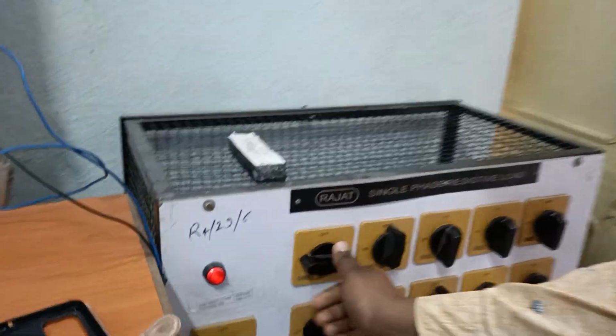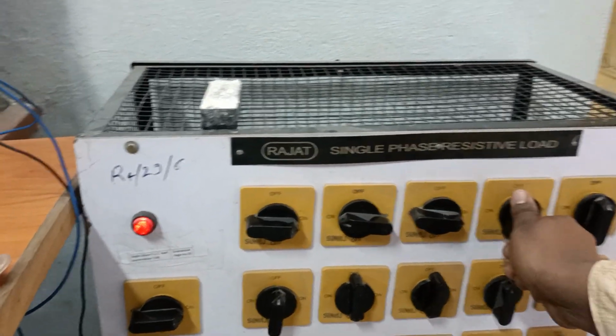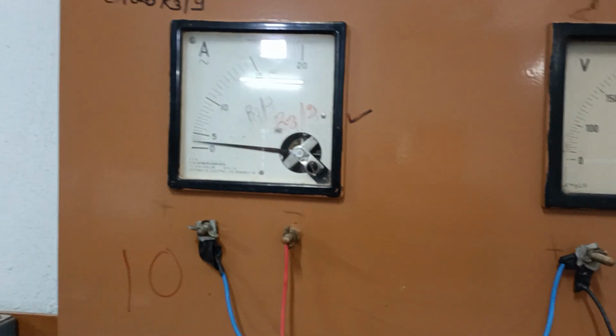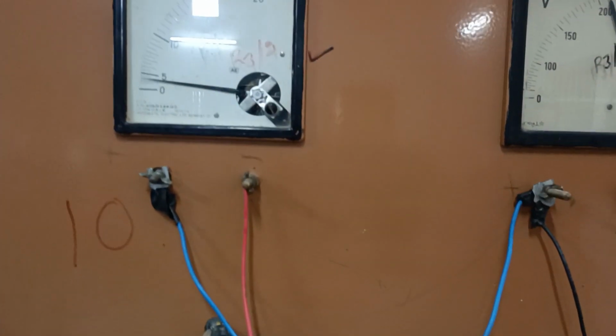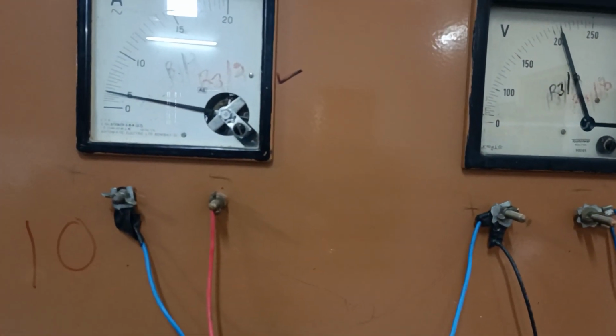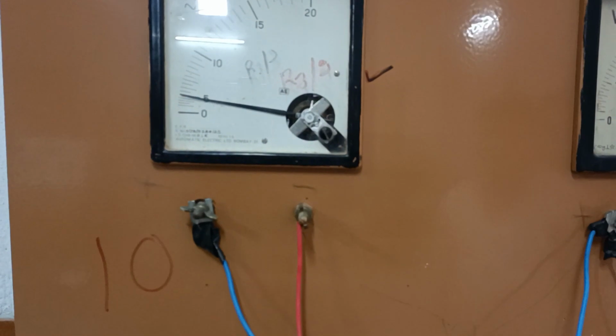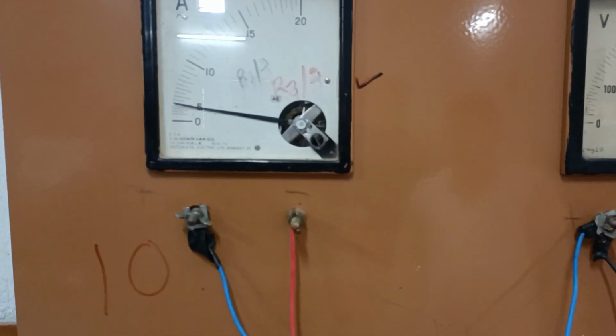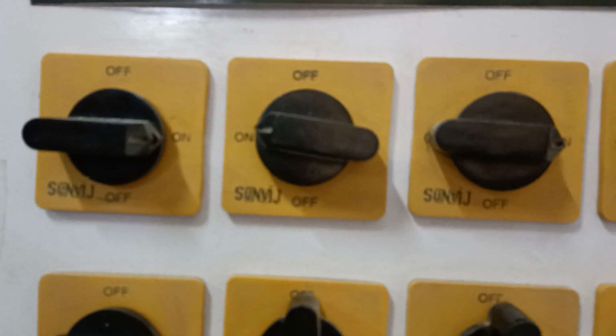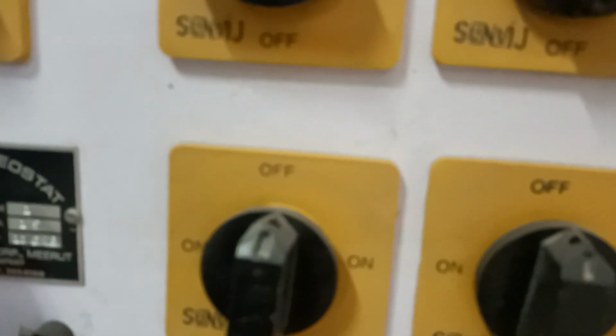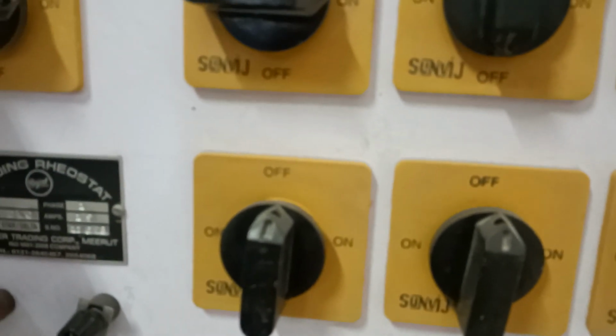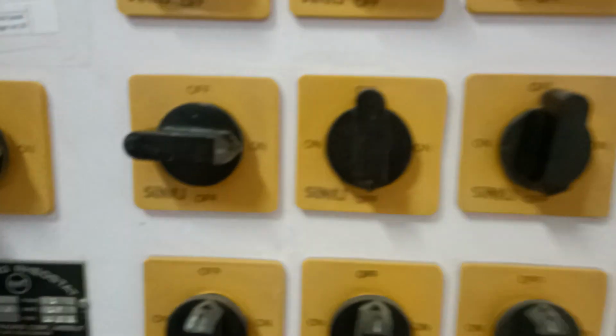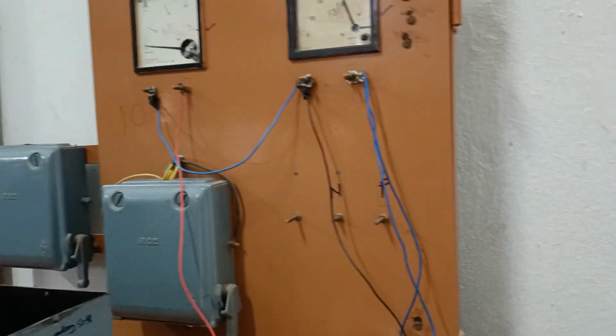Now I will increase the load. I will keep one eye over my ammeter, and stop where the current reaches 4.54 ampere. Now you can see I have approximately reached my rated secondary current, that is 4.54 ampere. You can see the load switches: this one is on, this is on, this is on, this is on, this is also on, and this is also on. In fact, I have used 6 switches to get this 4.54 ampere current. So this is called the full load condition.